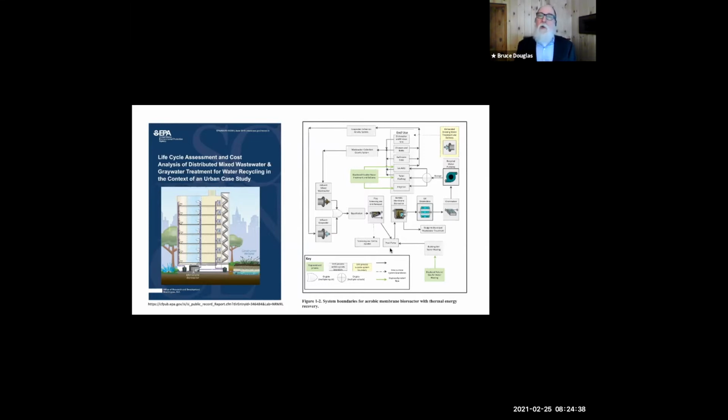If you look in the upper right-hand corner, there's a place below that. There's a recycled water pumping and storage circle right there, to the left of the pump. And so that's what we're going to be capturing from. So there's many ways to address this issue. What we like is the clean, clear nature of the reclaimed water. It's a really efficient way to gather the energy, to recover the thermal energy, and you don't have to deal with the biological growth and organic material clogging and masking your heat exchangers.